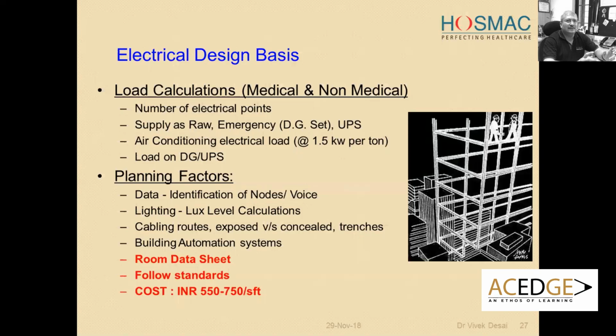Then there are certain lighting and lux level calculations given in a standard, which you can see off the internet, you will find that. Of course you have to then decide cabling routes - exposed versus concealed. If you want a concealed cable, then your interior design planning has to be complete in all respects, because otherwise you cannot keep chasing the walls. So in public hospitals we generally propose to give exposed only, because that's probably a better way to deal with it. But concealed, everyone likes it, no doubt about it.